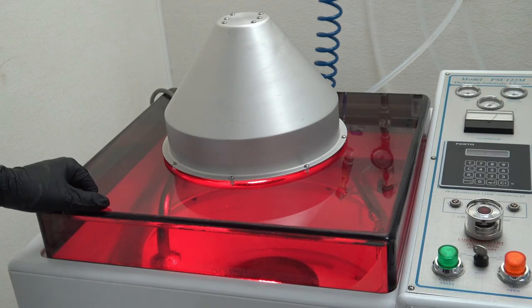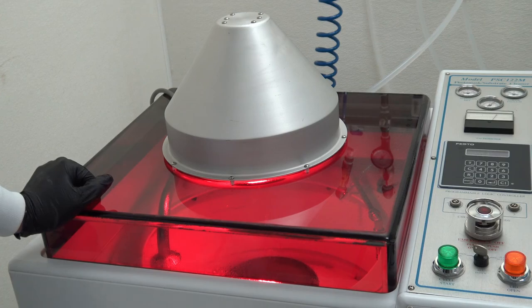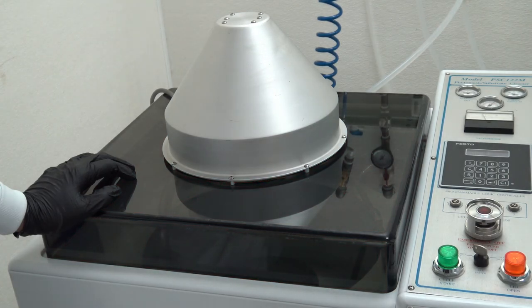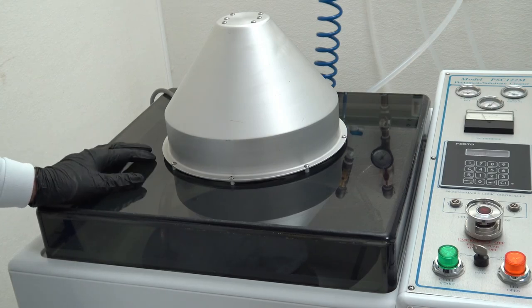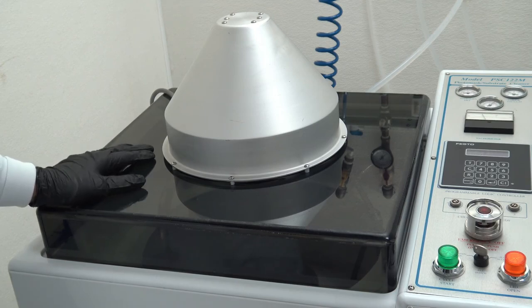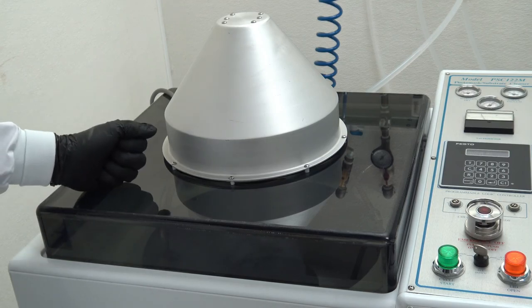So now here we have the heat lamp on. We have four more seconds of this before we're going to step over to our final spin down. Here we go. So now we're doing our final spin down and dry here. This really just allows the mask to cool down a little bit. It also allows us to step down the speed a little so we're not cutting off at 2,000 RPM. It's really more of a precautionary step that's going to assist with the drying a little bit, but it's not performing the main drying as I said. Main drying comes from N2 blow-off and the N2 heater.